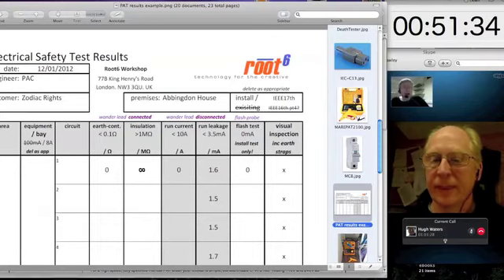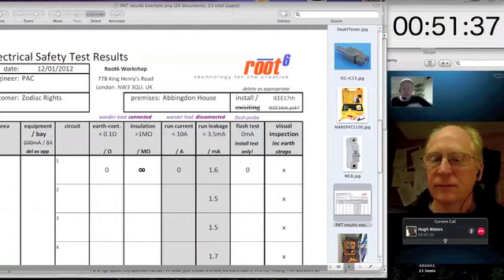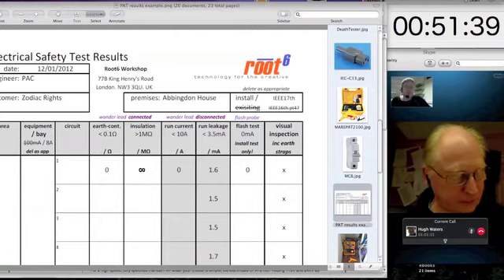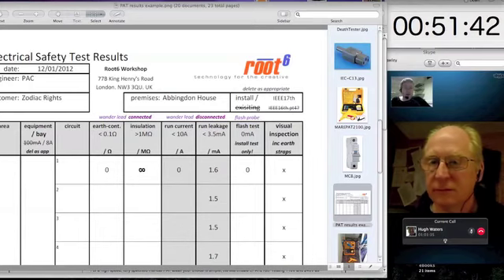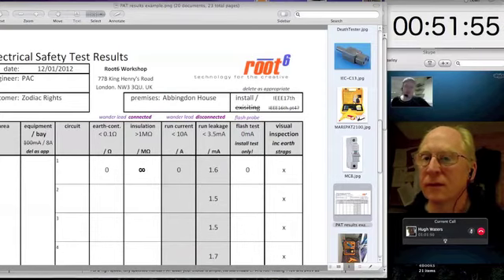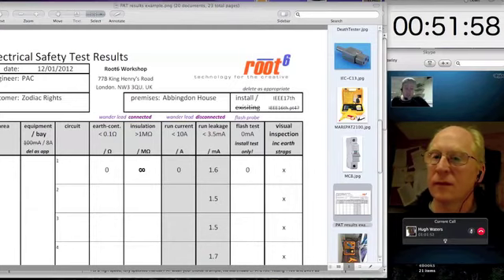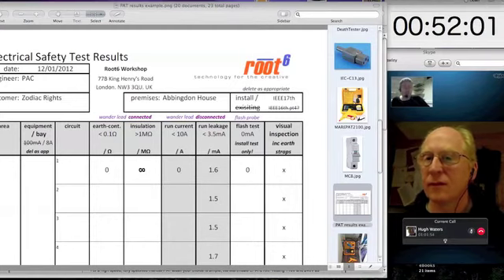Yeah. The next thing the machine tests, and so that's a press of the button and a little readout on the machine. And in fact, more elaborate machines will record that for you. And so an electrician can take his PAT tester, or an engineer can take his PAT tester, and he can go around and do 100 things, 100 pieces of equipment, 100 equipment cabinets, or a mixture thereof, and the machine will record all this for him, and he can dump that data out at the end of the day. The 2100 we use doesn't do that; it just displays it on a meter. And in fact, earlier machines had analog swing meters that would measure it for you, but the principle's all the same. Yeah.